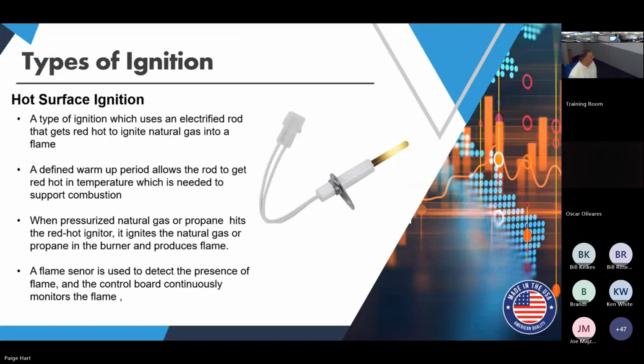Let's talk about ignition. We talked a little about hot surface ignition already. It's a type of ignition that uses an electrified rod that gets very hot, red hot, to ignite natural gas into a flame. There's usually a defined warm-up period—just like when you press the cigarette lighter in your car, you have to wait a few seconds for it to get cherry red before you can light your cigarette. Same idea here, maybe 7 seconds or so for that cal rod element to get cherry red and be ready to support ignition.